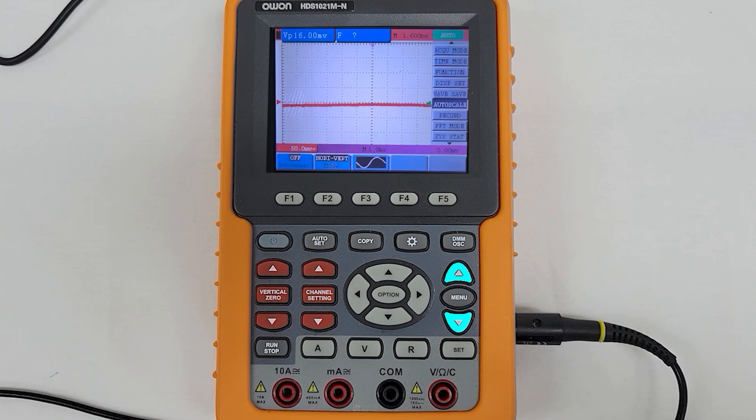Press the menu button, then scroll until CH setup is selected. Press the F1 button until coupling is set to AC. Press the F2 button until channel is set to on. Press the F3 button until probe is set to match the probe switch setting. Press the F4 button until inverted is set to off.